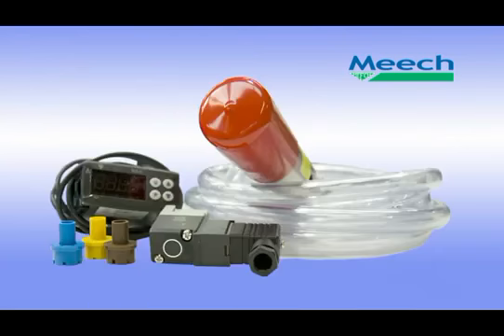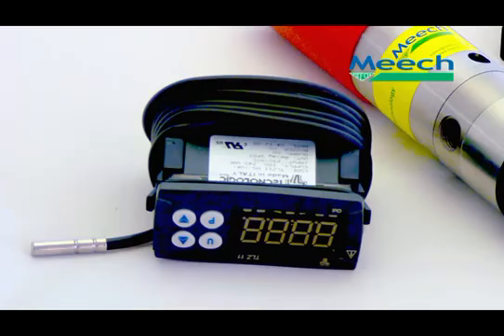The on and off temperature set points of the thermostat can be adjusted so the cabinet cooler can be set to run only when required. For example, if the cabinet overheats when its internal temperature reaches 32 degrees C, the digital thermostat can be set to turn the cabinet cooler on when the internal temperature reaches 29 degrees C and off once it is cooled down to 25 degrees C.